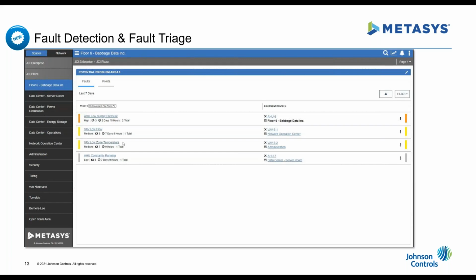What fault detection does is add to the algorithm so you can eliminate that alarm in favor of a fault. The fault looks at all the different trends coming from the air handler over time, whether it's during the occupied period, and whether it stays at a low condition longer than it should. It also looks at zones.